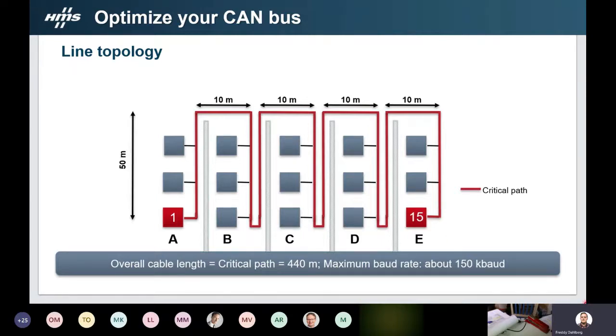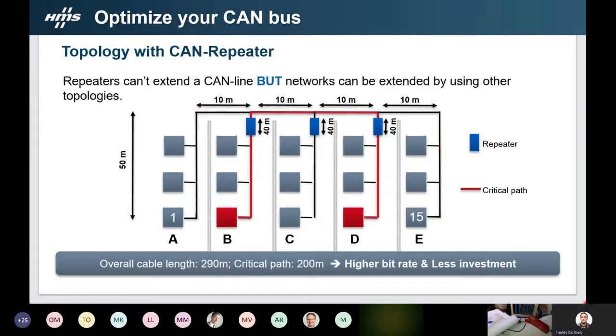So what about if you need more speed? If you add repeaters and change the topology a little bit, putting the repeaters here, the blue ones, the critical path is instead between node B and D. This gives a logical value of 200 meters, and you can easily use 250 kilobits instead of 150. In this case, you also save about 150 meters of cable, which might actually end up paying for the repeaters.